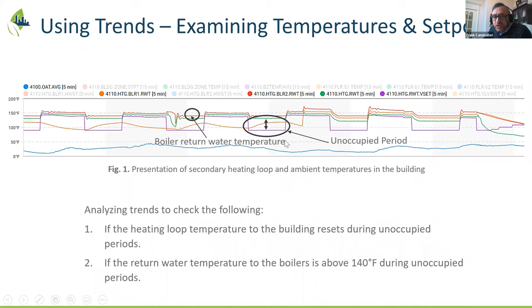So this is how you can use trends to understand if your building is working as intended. Again, the programming is such that the set point does reset, but actually it's not happening. The same thing on the return water temperature side, item number two - we have this line which is the boiler return water temperature to boiler number two in this specific facility.